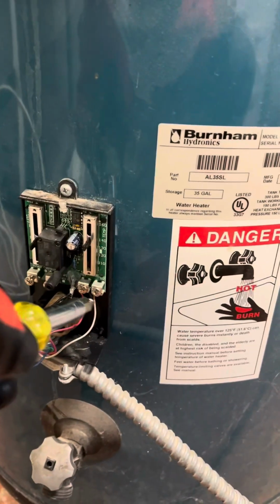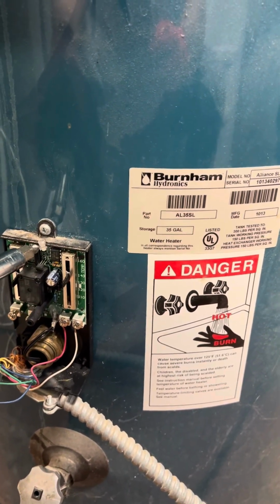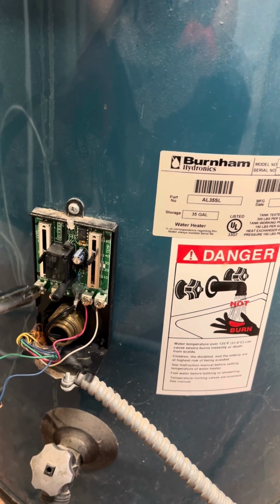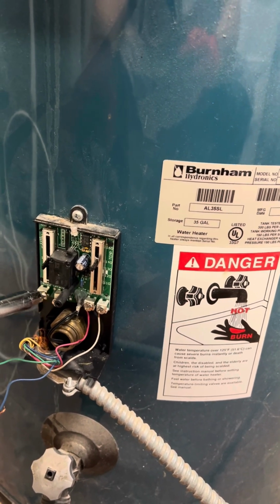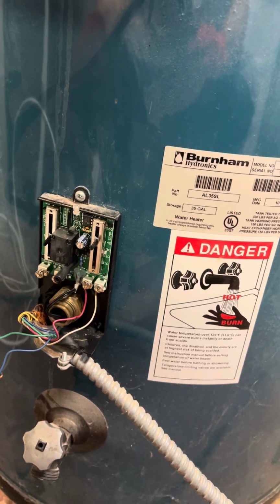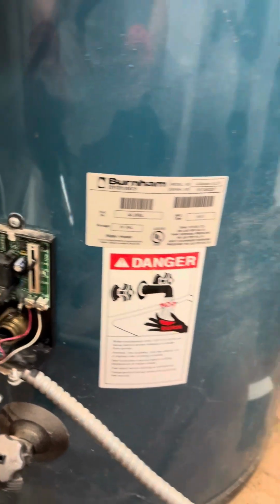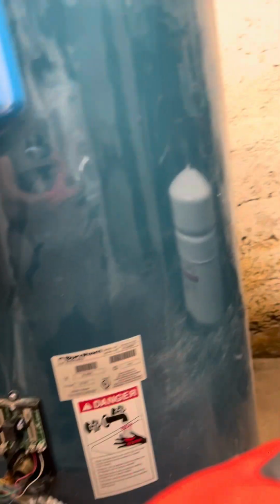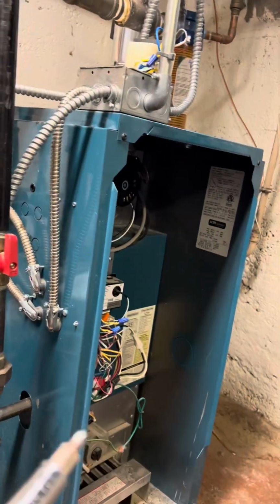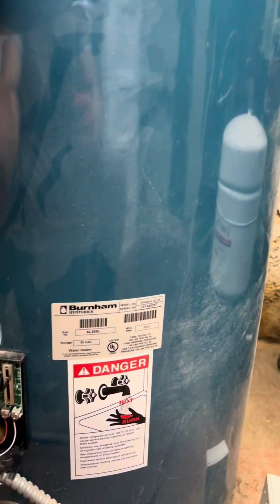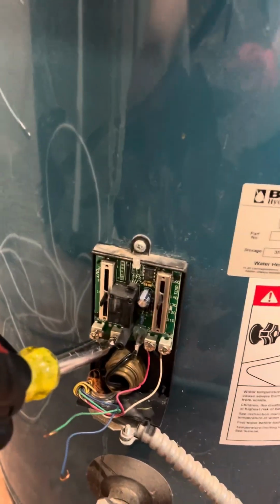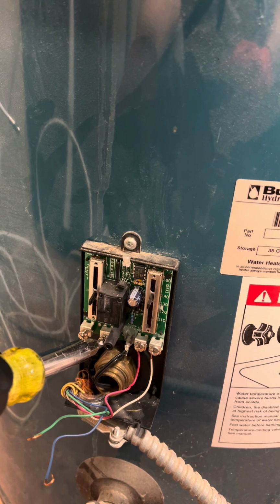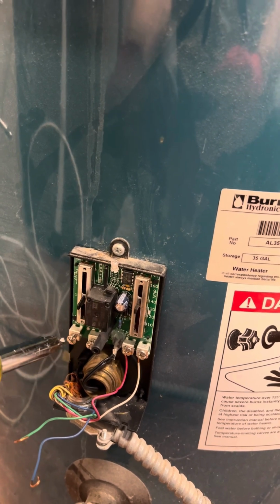Okay, that tells the boiler when to come on. And so that's strictly for the hot water. So this is getting 24 volts. This little light is supposed to be lit up, and when the water gets cold, these will come together like a switch. Put this wire to that wire, and then bring it right up there. So the one wire was bringing 24 volts from the boiler through and just sitting here. And then when this Aquastat closes, because it needs to have warm water, it'll close, connect to here.